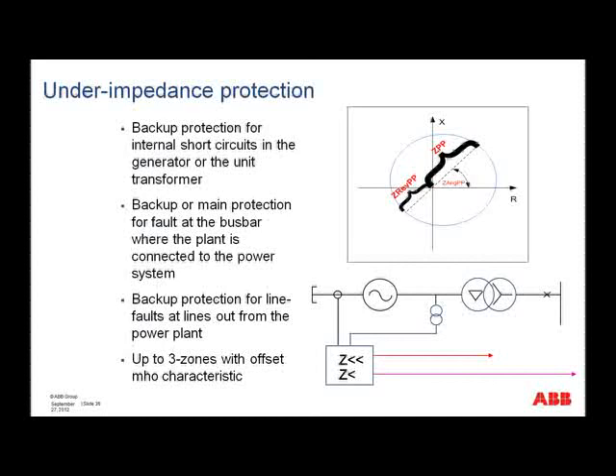All right, so that finishes off the differential protection. So we can look next at the under-impedance protection. Now, what is the purpose for this? Backup protection for internal short circuits in the generator or the unit transformer. This you have already seen in the slides that we've gone through, where there was the 87G or the 87O as the primary protection, but always as the reserve protection you saw that we had this under-impedance function.